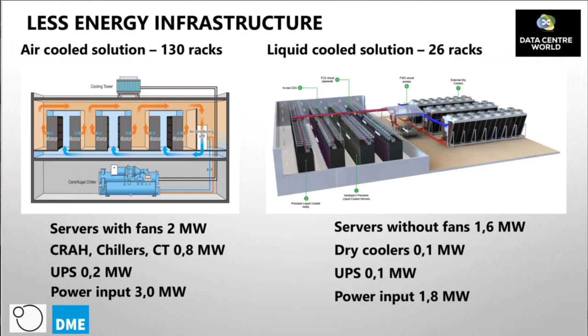In comparison, the other model has no fans, just heat pumps and dry coolers, consuming 400 kilowatt. So all in all, if you compare these two models, 1.2 megawatt less is consumed, but the performance is increased by 40%.